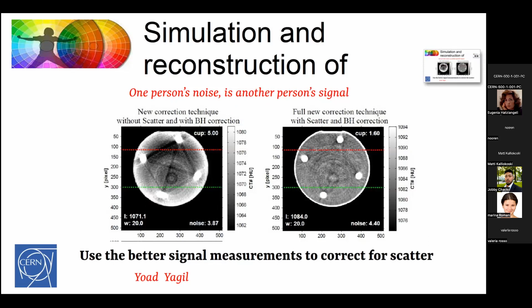Then Pierre talked about reconstruction. There's two parts to the way we take our raw data and turn it into an image. The first part, and they can be done in any order, is you have what are called sinograms. That's the raw projection data around the patient, and then you turn that into a 3D volume. That's called CT reconstruction. And the second part is to take the spectral nature, which is attenuation at different energies, and turn that into materials like fat, water, calcium, and iodine. And so that's a two-step problem.